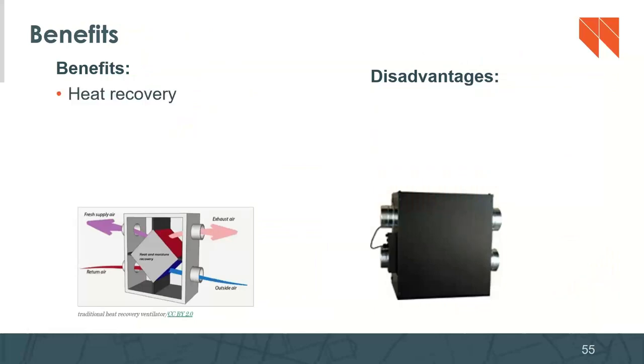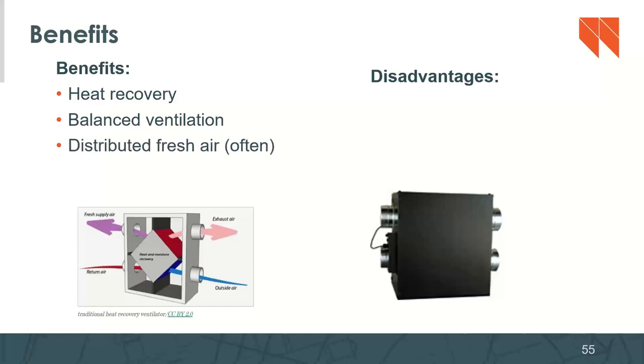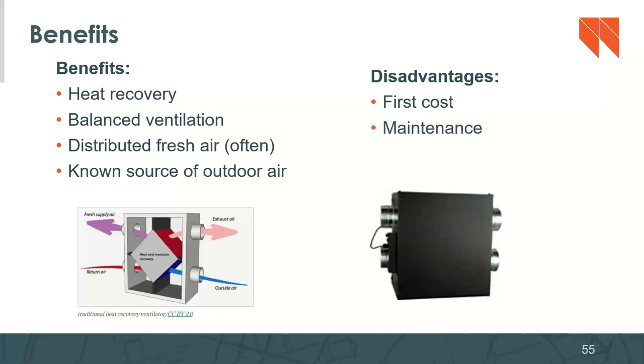What are some benefits of these? You get heat recovery, it's balanced ventilation. Usually it can be distributed fresh air, not always, there's a couple different designs, and you have a known source of this outdoor air. Some disadvantages: they're still kind of pricey, though costs have come down. There's additional maintenance, i.e. changing the filters, and there can be integration issues. We're going to talk about design considerations, but that's what we mean by integration issues. We want to share with you what we've seen, what works, what doesn't, and what you might be able to take back and incorporate into your own practice.